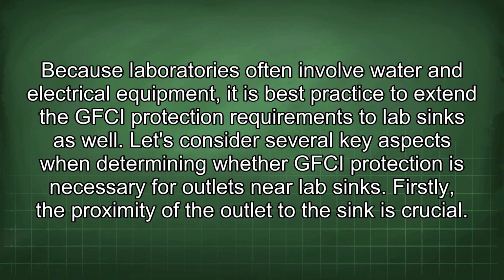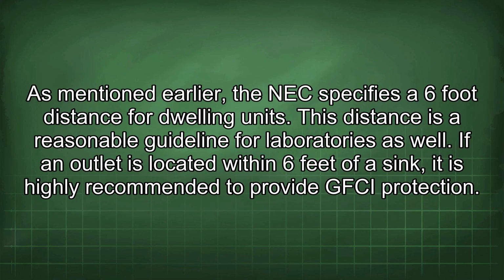Firstly, the proximity of the outlet to the sink is crucial. As mentioned earlier, the NEC specifies a 6-foot distance for dwelling units. This distance is a reasonable guideline for laboratories as well. If an outlet is located within 6 feet of a sink, it is highly recommended to provide GFCI protection.